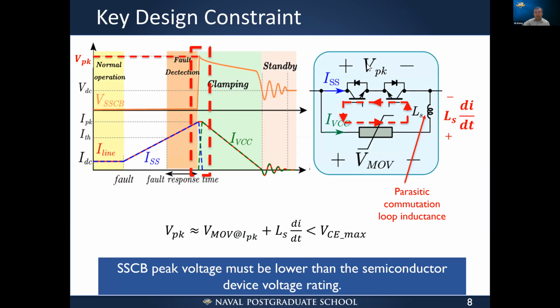So then what are the design constraints for the solid-state circuit breakers? The key design constraint is that under no condition can the semiconductor devices be exposed to more than they can withstand in transient voltage. As you can see, once we turn off the devices, there is a peak voltage across the solid-state circuit breaker. The peak voltage can be estimated as the clamping voltage, the voltage across the MOV where the MOV carries a high peak current, plus the L di/dt transient voltage applied to the parasitic commutation loop inductance. This is a parasitic inductance between the MOVs and the IGBT.